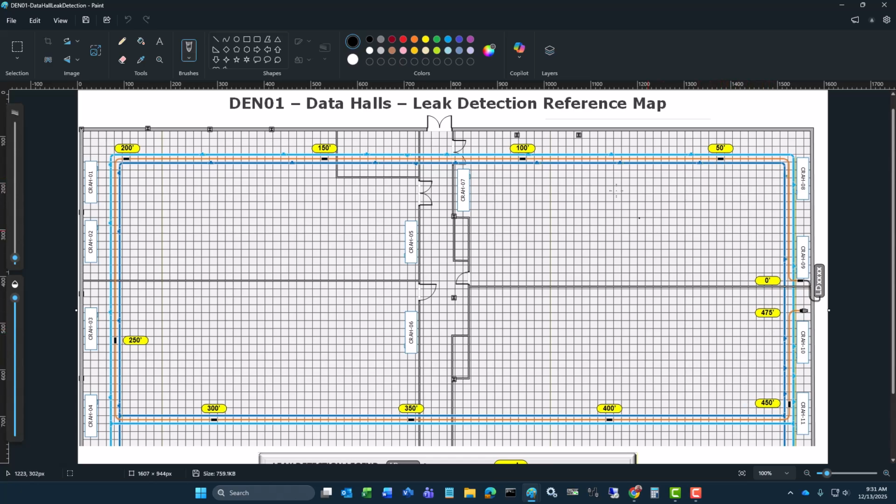So you can see I am going around the outer perimeter where the primary leaks would occur, the way this cable was laid out, and then there was a 25-foot section at the very end here, bringing us up to a total of 475. This is a JPEG image. I'll show you the image requirements once we get into the configuration of the controller. You just need to have some sort of background image showing the routing of the cable, and then I'll go into the details of what key things you need when mapping this.